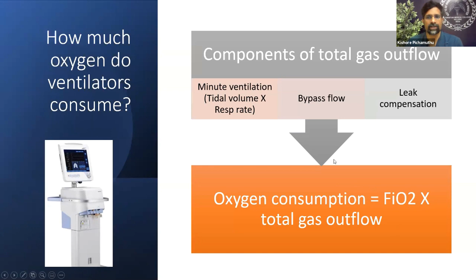Even though ventilator circuits should be leak-proof, there is always some leak here or there. And so it compensates, and this information about how much leak is being compensated by additional flow should be available on the ventilator screen as well. So this oxygen consumption is basically the FiO2 fraction times this total gas flow. As an example, if the minute ventilation of the patient is 10 liters per minute, and there seems to be a 2 liters per minute leak flow, and base flow, for example, most of the ventilators that I have are Hamilton ventilators, and they have about a base flow of 6 liters per minute. And if the fraction of inspired oxygen is 0.6, then the total consumption would be 0.6 times the total gas outflow. So that would be about 648 liters per hour.